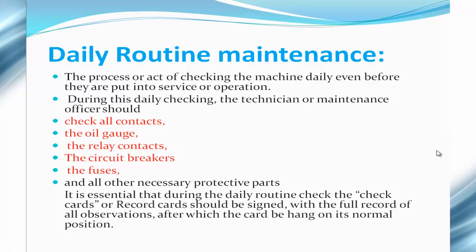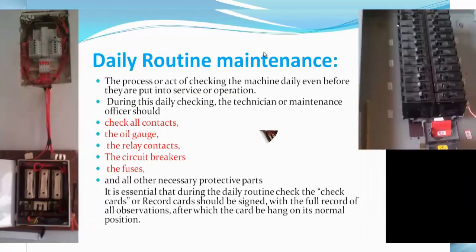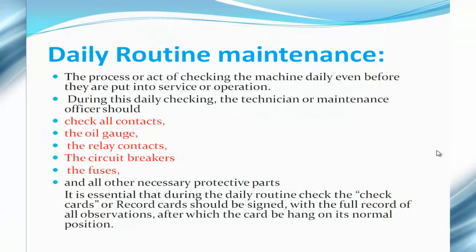The daily routine maintenance, just as the name implies, is the type of maintenance carried out on a daily basis. Even before the machine is put to use each day, you have to inspect it to make sure it is in proper condition and order. The technician must check all contacts, the oil gauge, relay contacts, circuit breakers, fuses, and other necessary protective parts. Check cards or record cards should be signed with full observations recorded, after which the card is returned to its normal position.